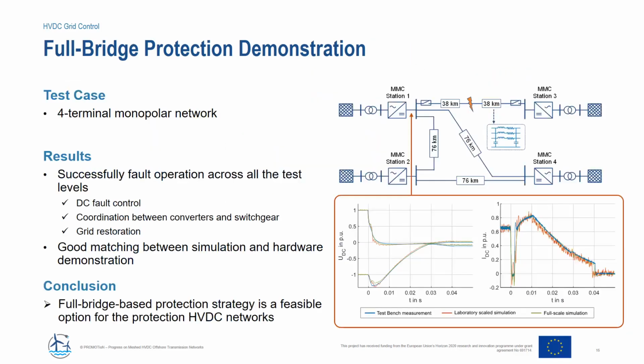So let me now quickly guide you through the demonstration of an exemplary test case in a 4-terminal monopolar HVDC network, and the fault here is an exemplary fault in the middle of the line between station 3 and station 1. In the figure you can see the DC voltage as well as the DC current at station 1, on the one hand in blue for the MMC test bench measurement, then for the laboratory scale simulation and for the full scale simulation. And you can see overall at first glance that the results match very well.